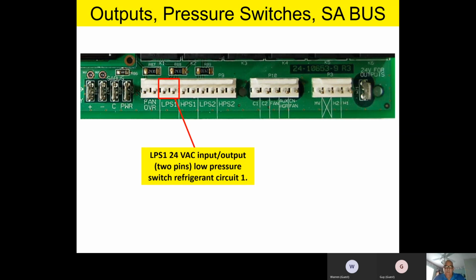hooked up. Now, team, it should be noted that these safety circuits right here, this high and low pressure safety circuits, these are hard 24-volt safety circuits. Now, what I mean by that is if you open one of these circuits up, it results in compressor and unit shutdown. And so these are hard safety circuits. They're actually wired in just like a regular pressure switch. So it's just a click, click pressure switch, high pressure switch, low pressure switch, input to the board, and they are 24-volt input and output for those pressure circuits or those safety circuits.